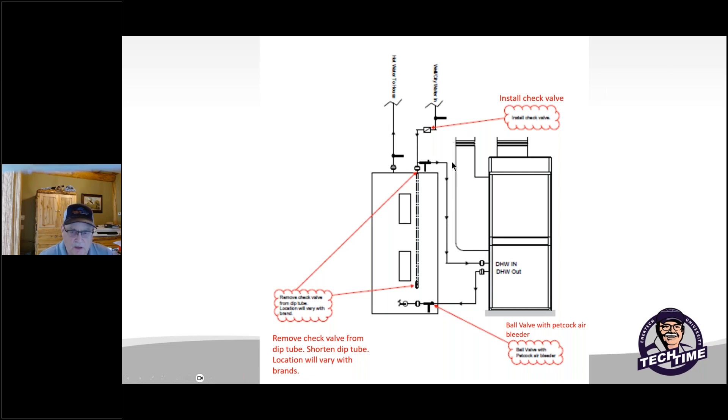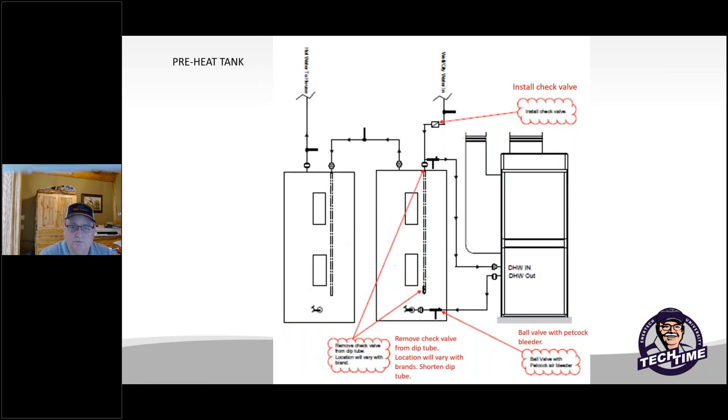Another typical way we do is with a pre-heat tank. Typically we would not have this hooked up to electricity or gas to allow the desuperheater hot water generator all the time it can to preheat the water before it goes into the second actual water heating tank. This is the best way, the most efficient way of utilizing the geothermal hot water system. Space is always considered an issue.